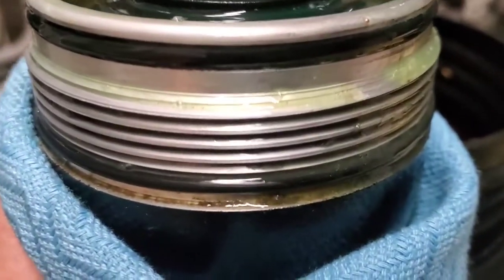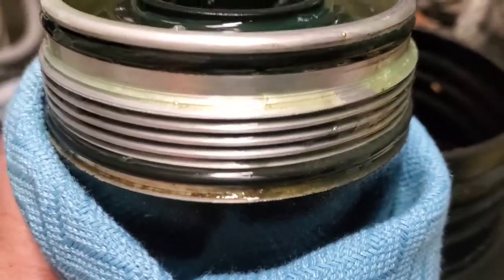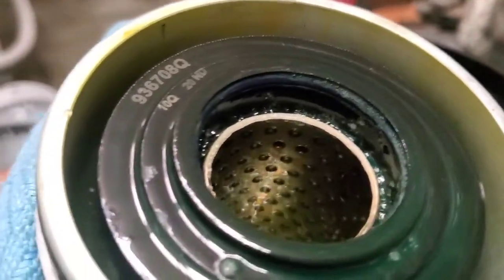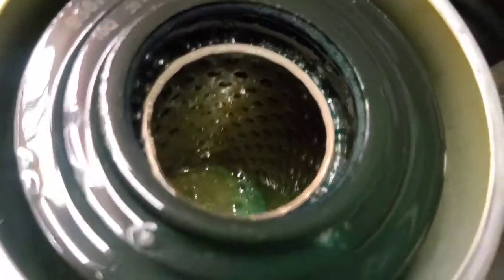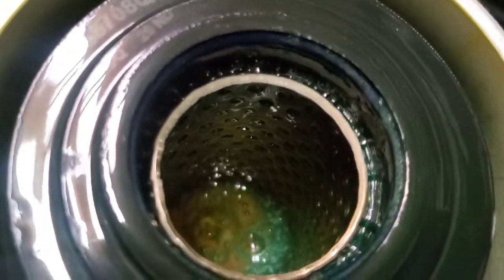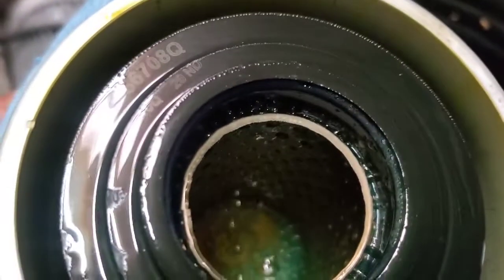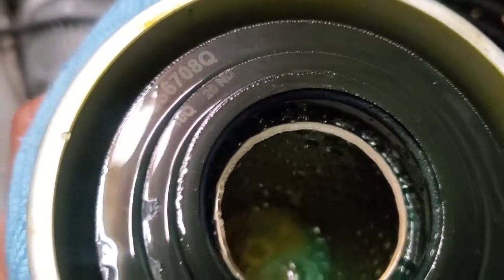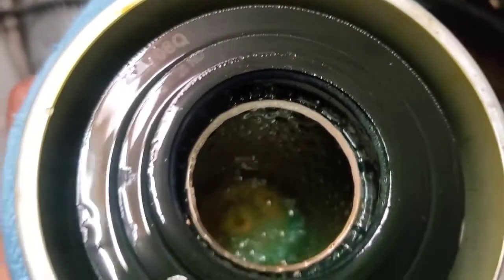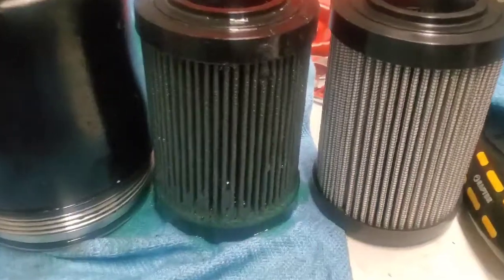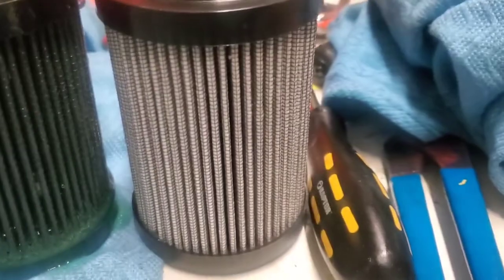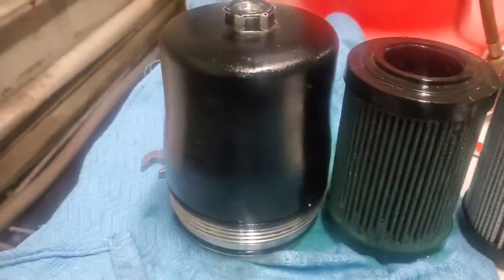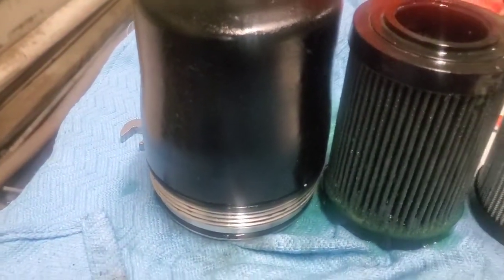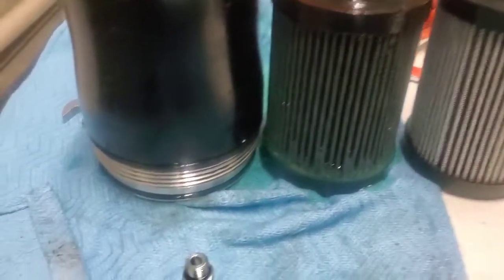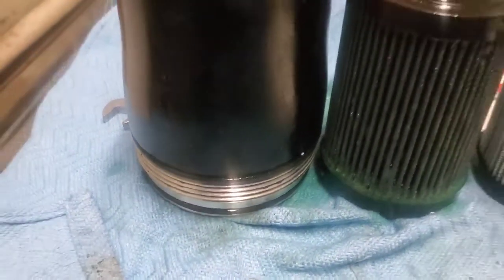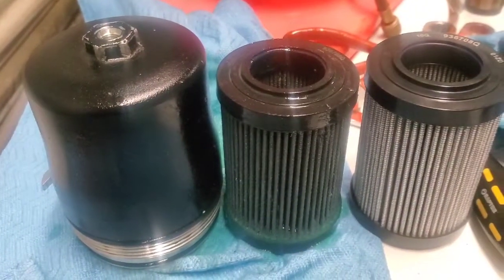We're also going to replace these O-rings every time so they don't leak, get everything cleaned up. We're also going to pay attention to what that filter looks like, and if there's any pieces of metal material that's in the bottom of that canister, indicating we may have some metal on metal friction and wear that we need to be concerned about. All right, so here's the old filter, and here's the new filter. We'll stick that back in the canister, change the O-rings, get everything cleaned up, put a little nylon on the surfaces here, the threading surfaces, and get this put back together.